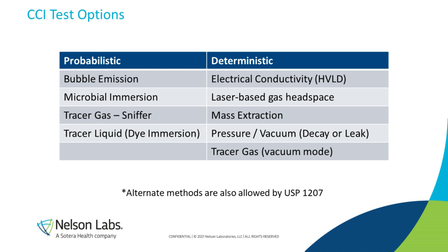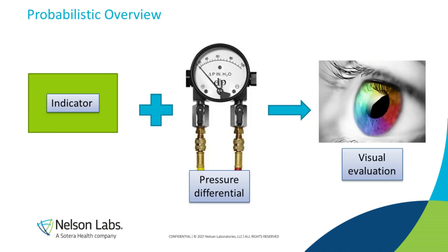The probabilistic methods work like this: there's some kind of an indicator — whether it's air, dye, microbes, or a gas — and then we create a pressure differential using either a vacuum or pressure. This indicator moves through any defects, and then we do some kind of evaluation, usually visual: do I see bubbles? Is there dye inside the container? Is there microbial growth in a previously clear media? This tells us if the result is a pass or a fail.